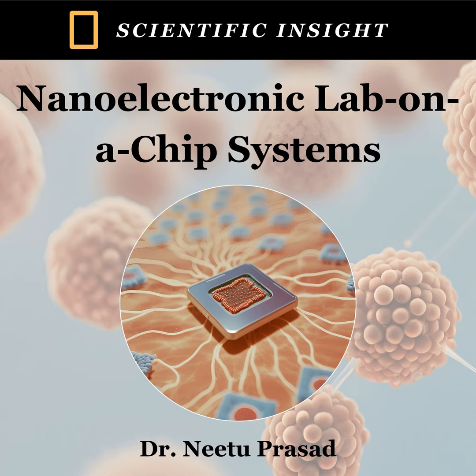These systems utilize microfluidic technology to manipulate small volumes of fluids through tiny channels and chambers on the chip. By integrating sensors, pumps, valves, and other components, LOC devices can carry out complex biochemical reactions and analysis with high precision and efficiency. The process begins when a biological sample, such as blood or saliva, is introduced into the chip through an inlet. This sample may be pre-treated to isolate specific components or mixed with reagents for further processing.